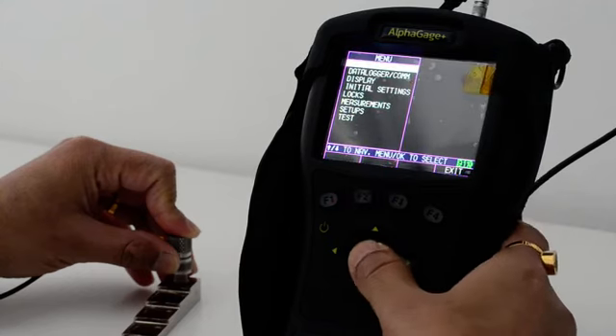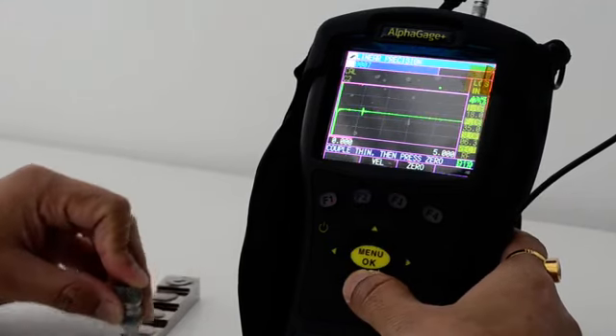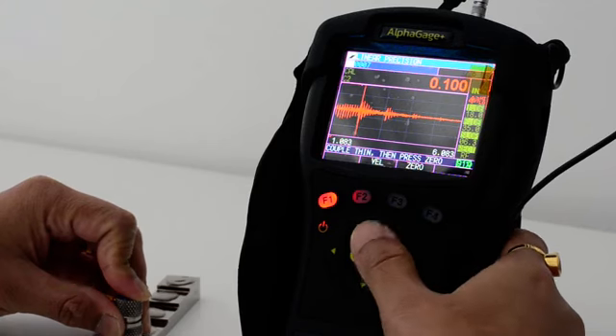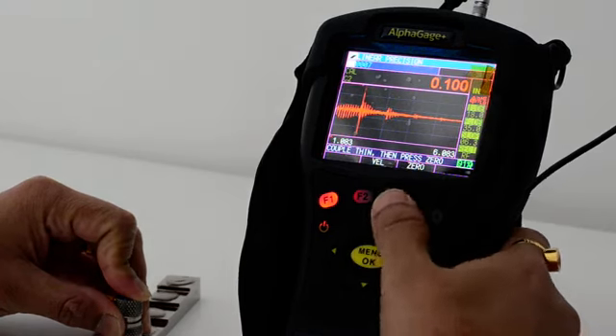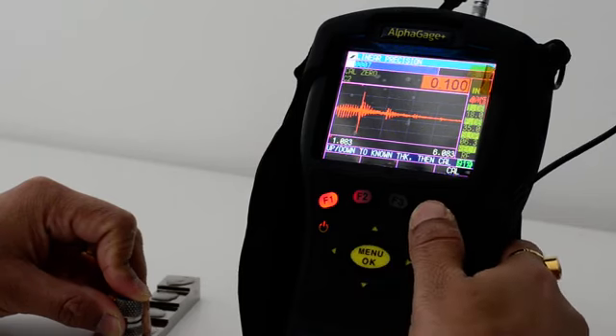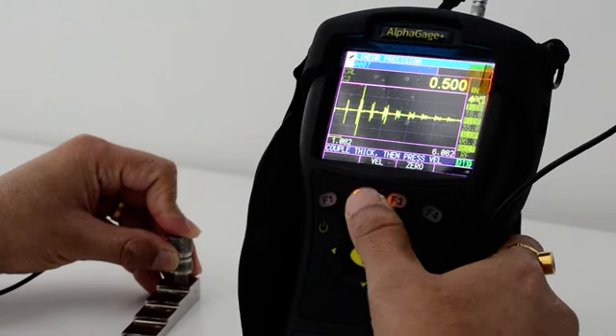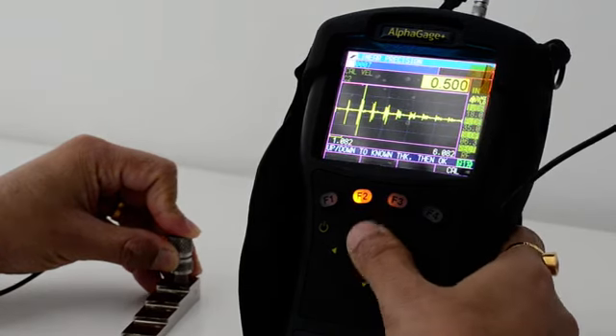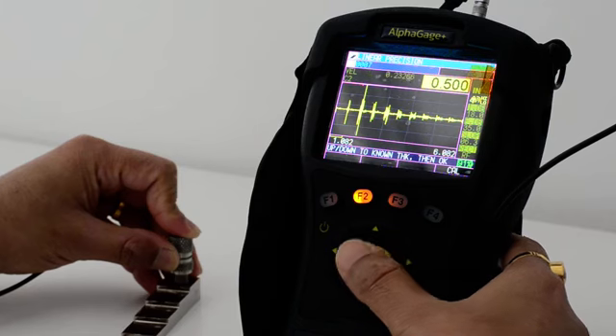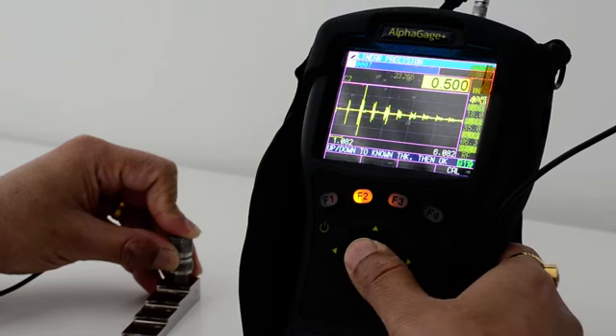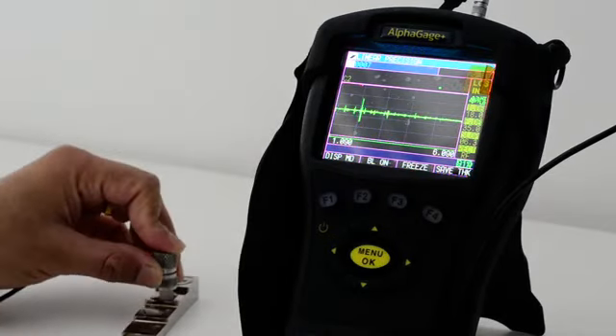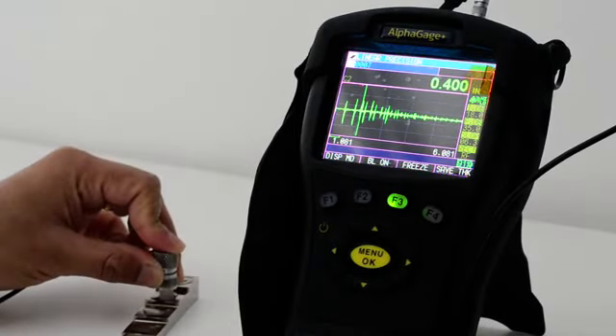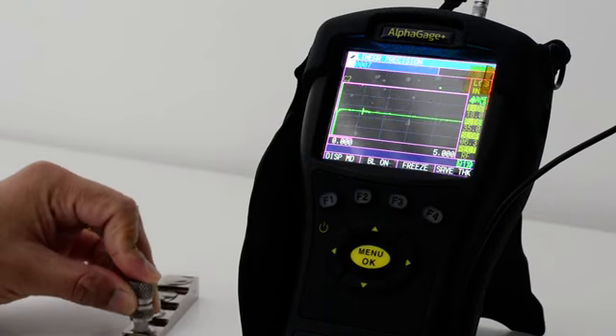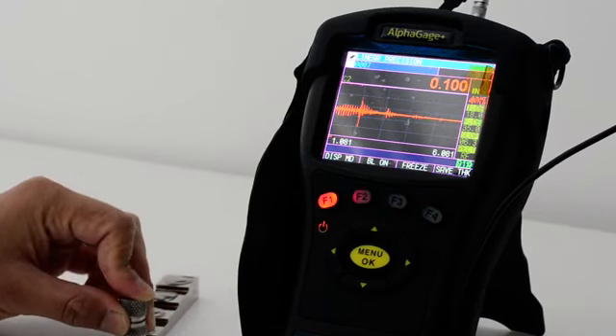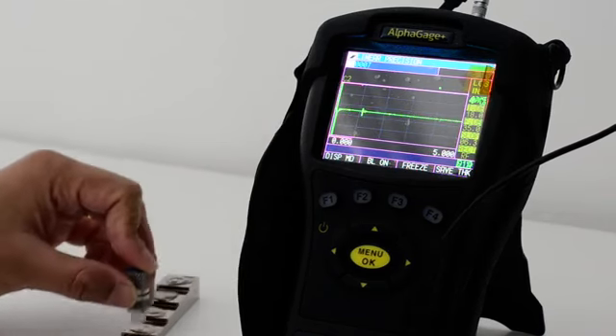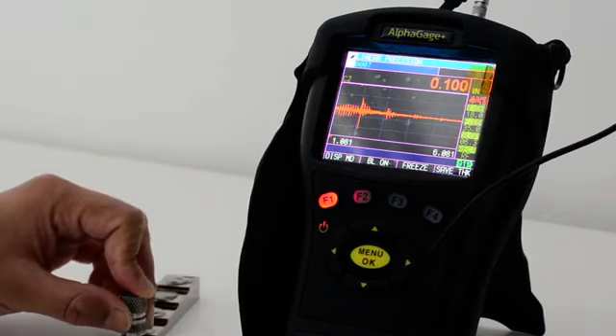Okay, so let me redo the calibration first. Go to the thin, press 0, change it, and then press cal. Go to the thick standard, do some changes, and then press OK. Once the calibration is done, you can check the rest of the thickness: 0.4 is coming right, 0.3 is coming right, 0.2 is coming right. So my instrument is calibrated for a thickness range from 0.5 inches to 0.1 inches.